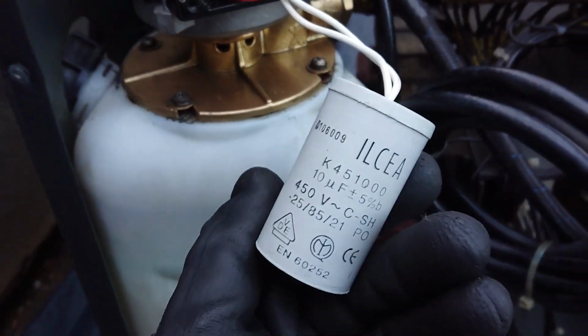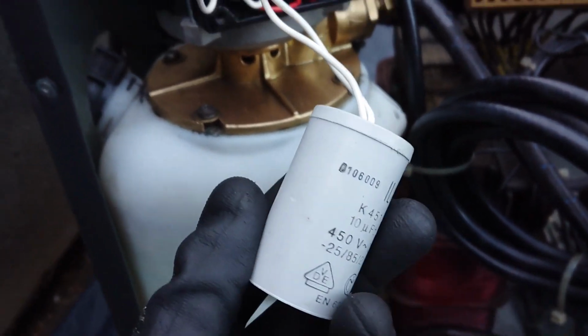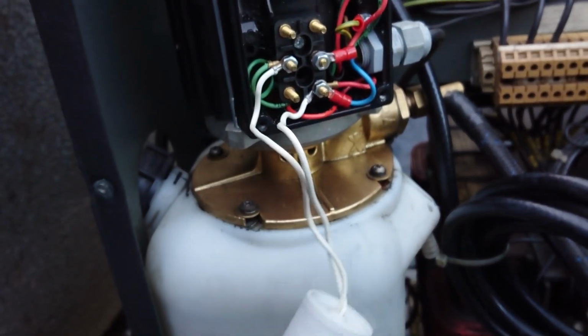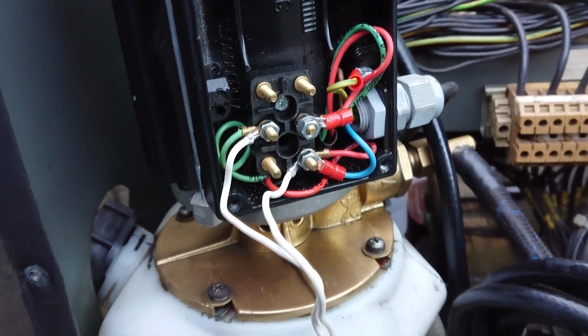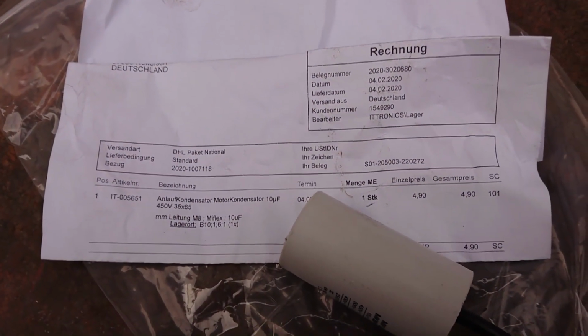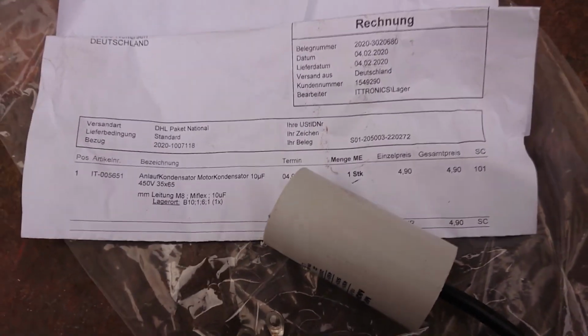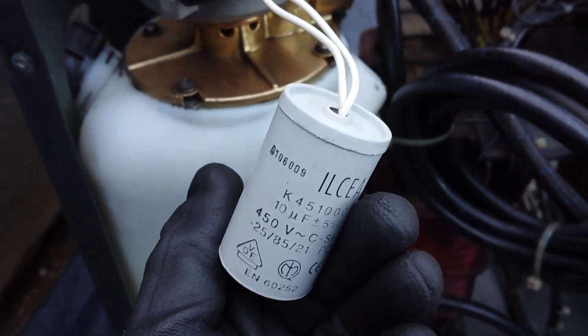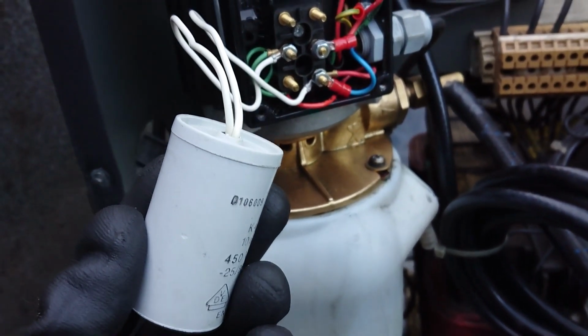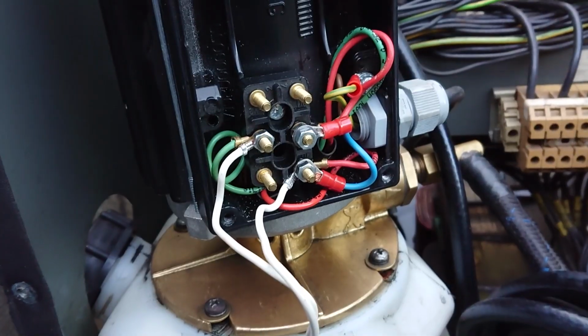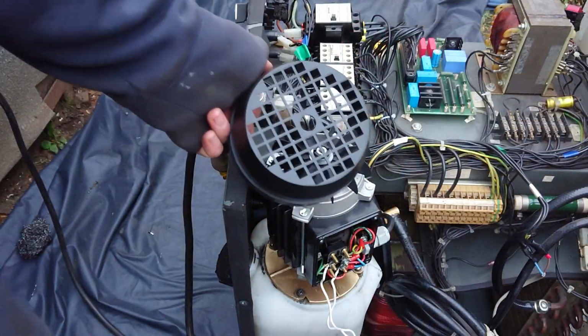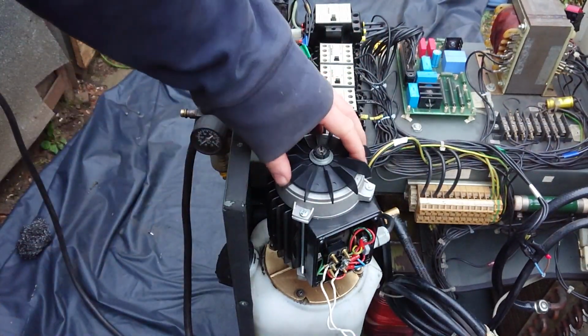But that idea turned out to be wrong. There is a capacitor inside this black enclosure. So here is my next suspicion. The capacitor in that bag is used, but it's not old at all. Someone replaced it because the pump wasn't turning. But whoever did that was looking in the wrong place, because upon removing the fan guard here on top, it's obvious that it's not an electrical problem, but a mechanical one.